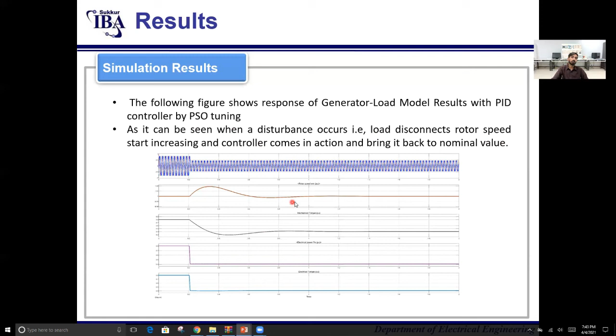The following figure shows the response of the generator model with the PID controller tuned by PSO. As can be seen, when a disturbance occurs, load disconnects, rotor speed starts increasing, and the controller comes into action and brings it back to the nominal value. And this is the best response given by the PSO algorithm.